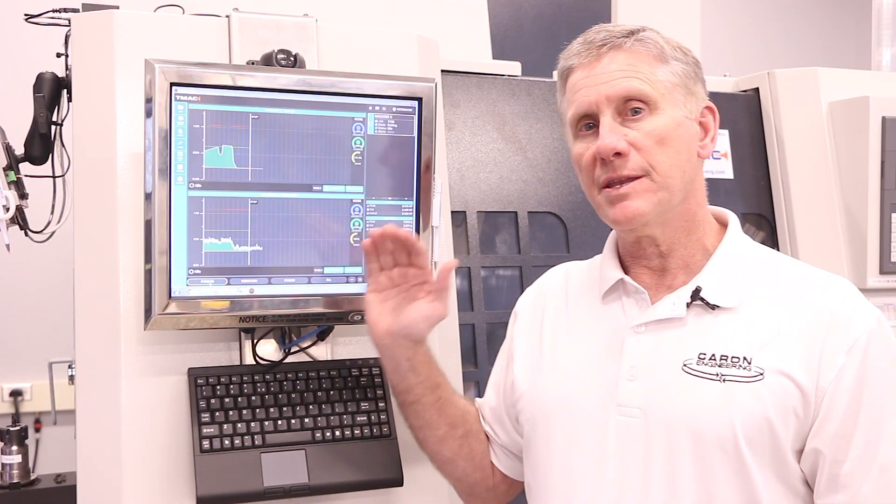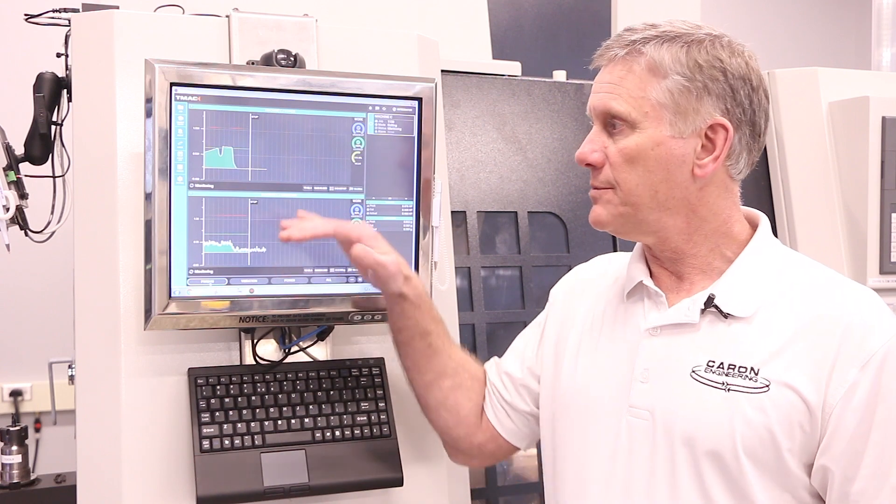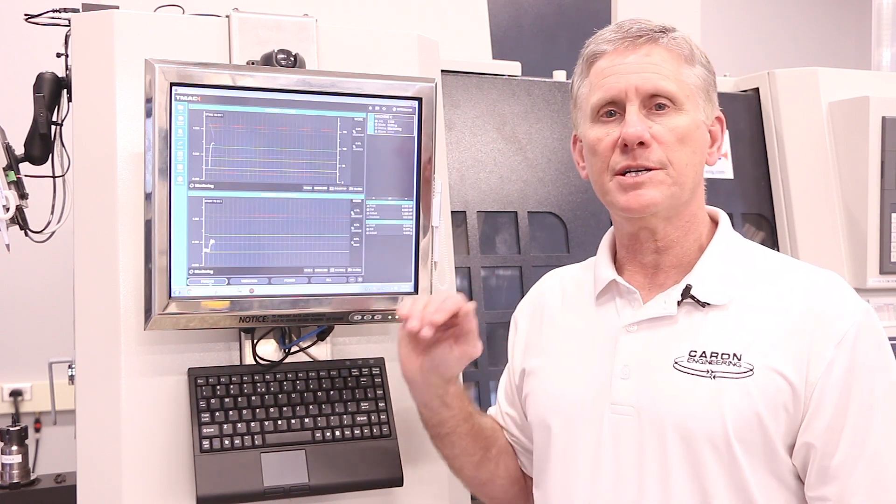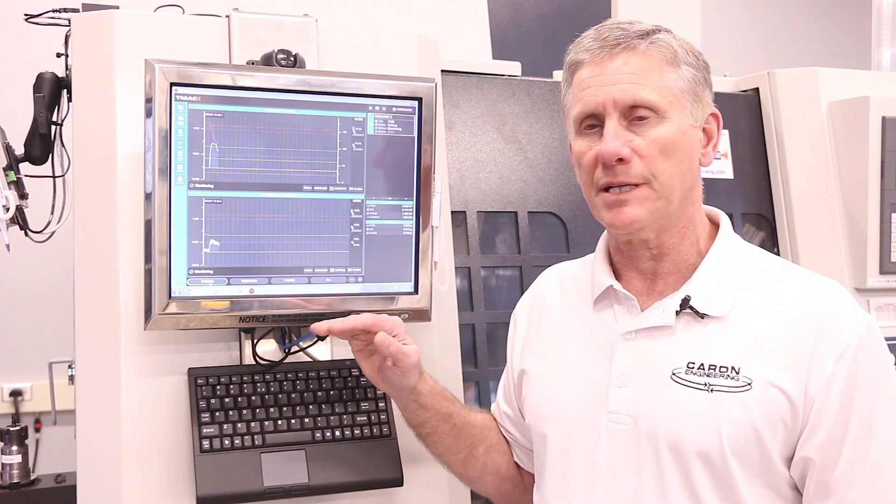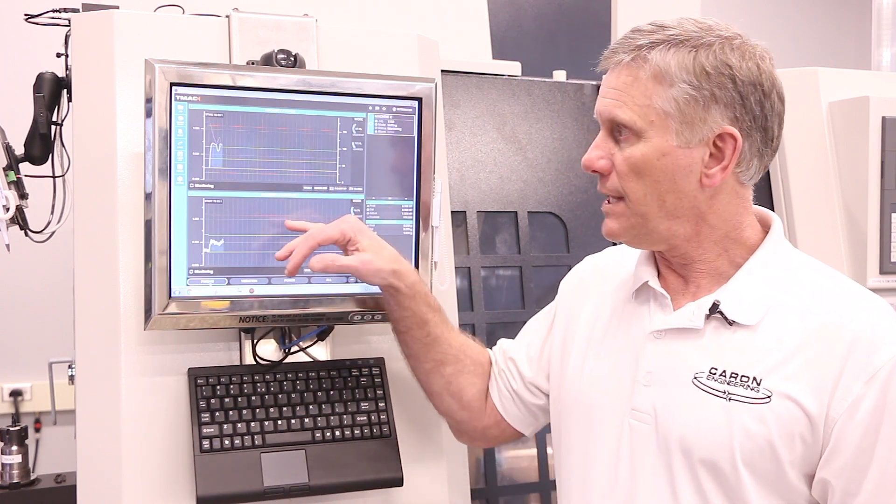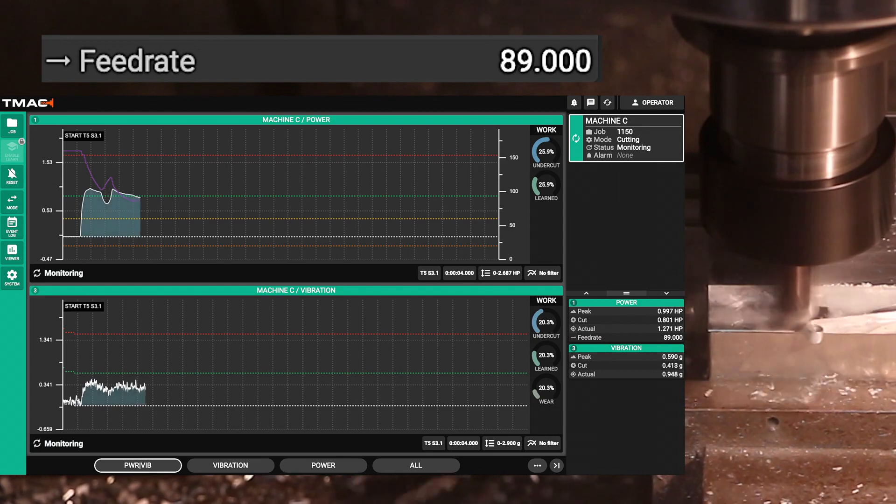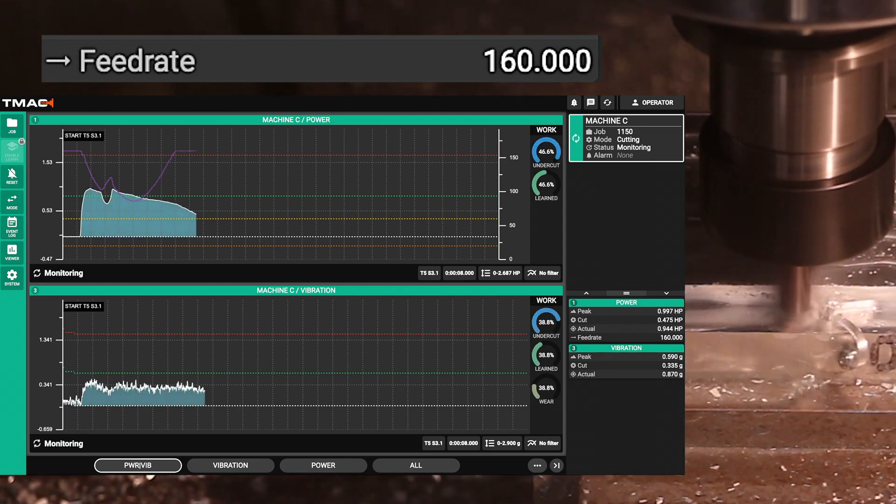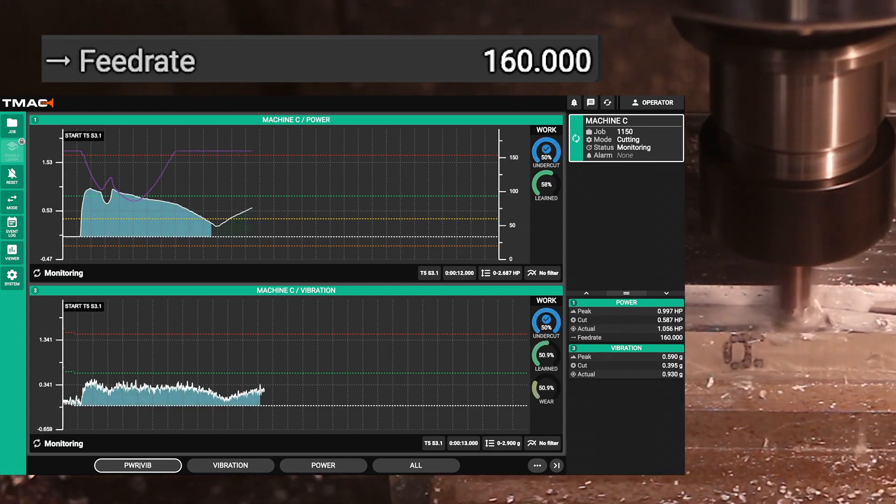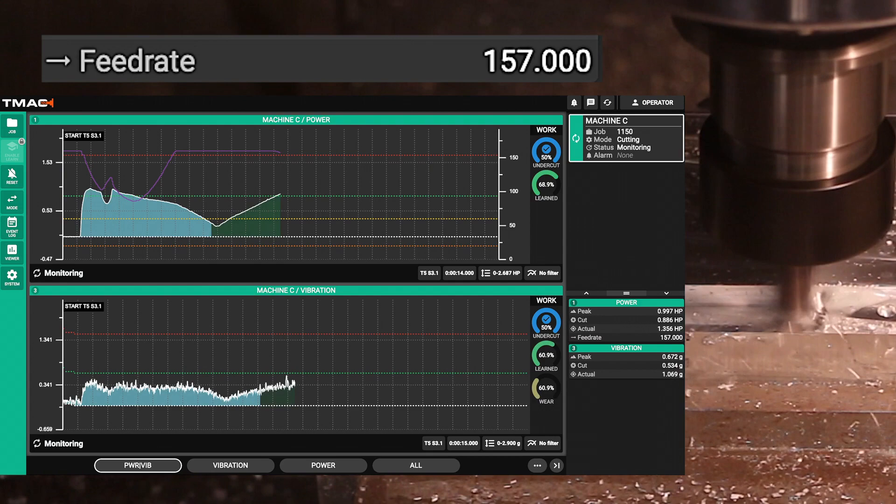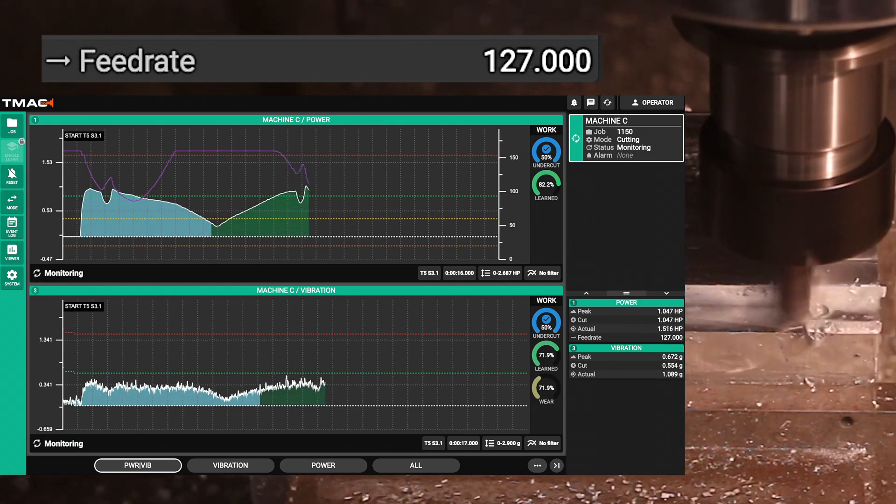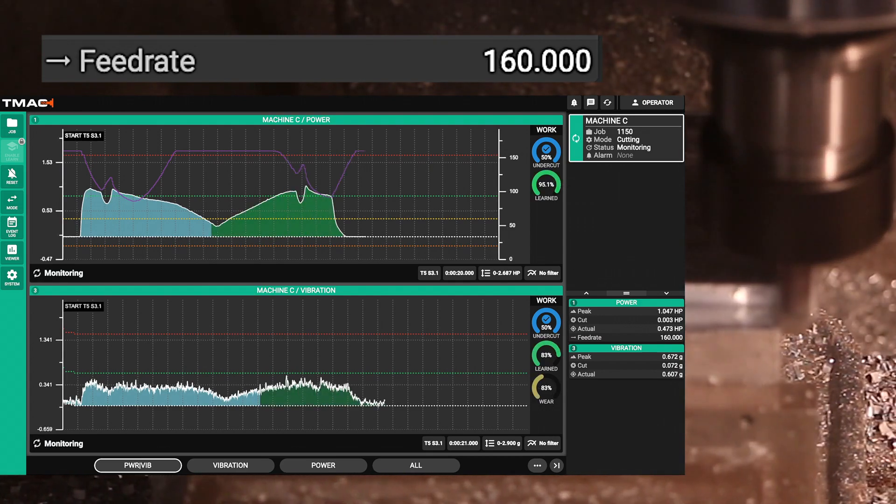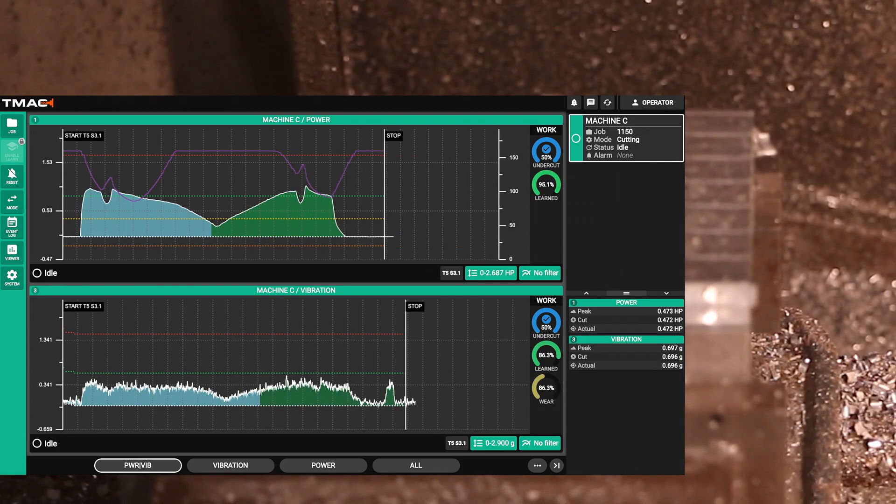As you can see by this view we're actually monitoring power and vibration simultaneously. This allows us to look at the health of vibration of the tool while the tool is doing adaptive cutting, giving us some more advanced analysis of what's happening with this tool in the cut.